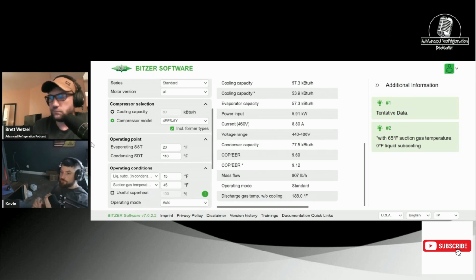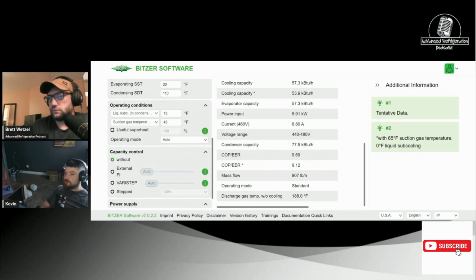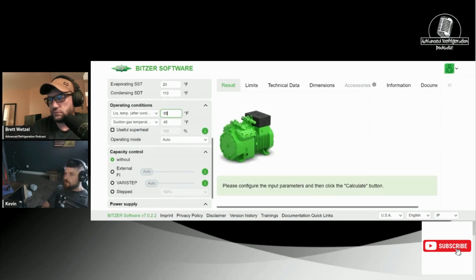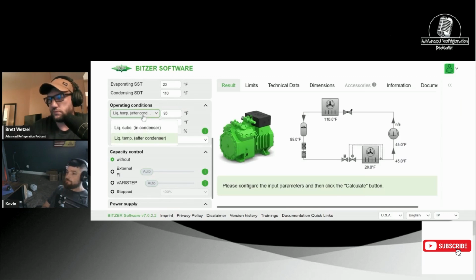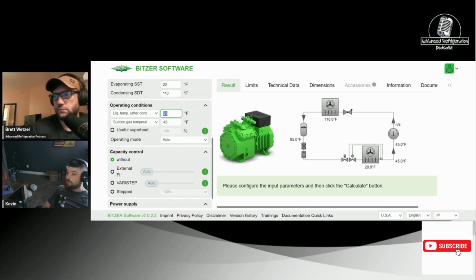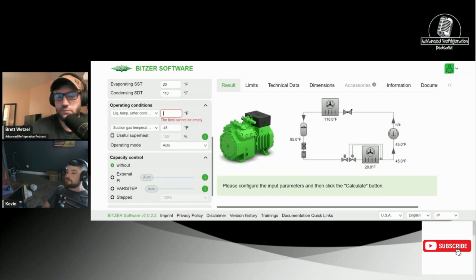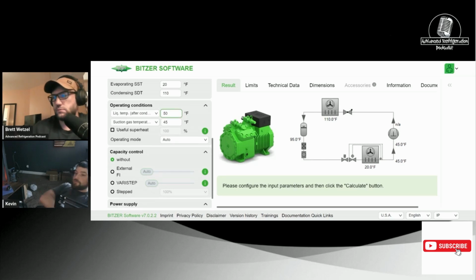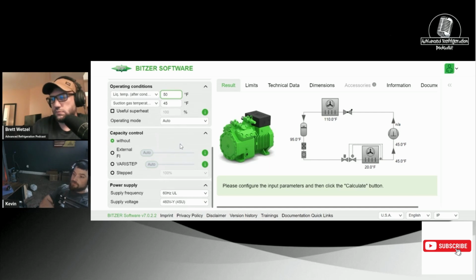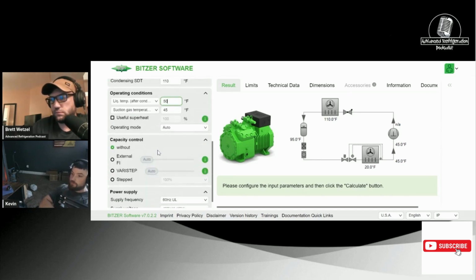So this is where troubleshooting is a huge help for discharge temp issues. Over the weekend, I was having issues with a Bitzer compressor, and what I thought would have been excessive discharge temps at the CO2 store, it was hitting like 230 at times, but it was right within spec of what Bitzer was calling it for it to run. I would have thought it was running hot, and it was within 10 degrees of what the discharge should be. That's why this is a huge troubleshooting tool for you to look through.